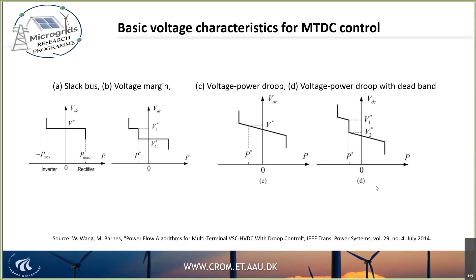In offshore wind, we use type 4 wind turbines, meaning all these turbines are connected to fully rated converters. So you just rectify and use an inverter, and the wind turbine side and the grid side are to a large extent decoupled. This lets us add many features on the inverter side, one of them being islanded and black start operation.